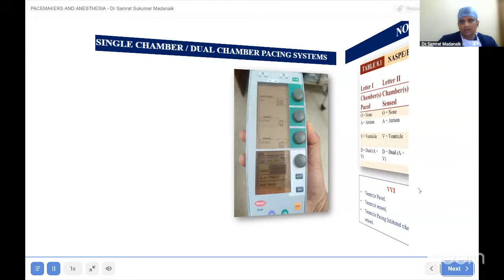So basically, the North American Society for Pacing and Electrophysiology and the British Pacing and Electrophysiology Group, that is the NASPE or BPEG group, devised the generic pacemaker identification code. And basically, there are 5 letters for naming these pacing systems. The first letter always denotes which chambers are paced. The second letter denotes which chambers are sensed. The third letter denotes the mode of response. The fourth letter tells us about the programmability and the rate modulation.